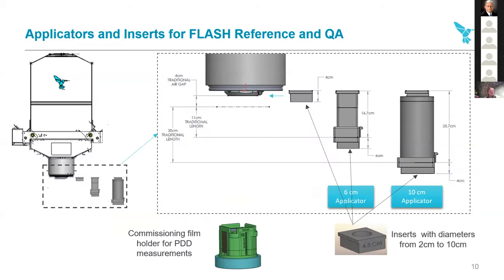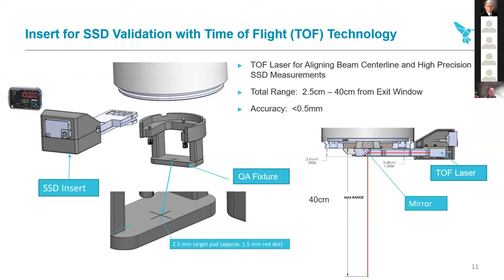The system comes with a set of applicators and inserts for reference QA. We chose three different points and a couple of different diameter field sizes to show the range of operation and compare what we make at the factory to what people see in the field, so they can do acceptance testing confidently. We also make a novel commissioning film holder designed to go in the water tank, attach to the end of the applicators, and do PDDs and quick shots on multiple films at once without tedious measurements — making QA faster and easier. It also comes with a time-of-flight laser system for accurate distance measurements when you have attachments for mice or human treatments, giving you an accurate distance range at the end of the collimator.